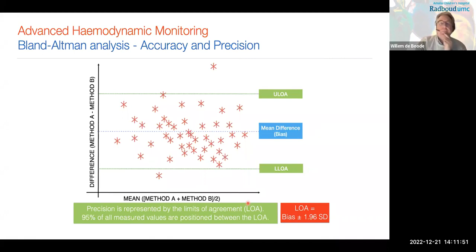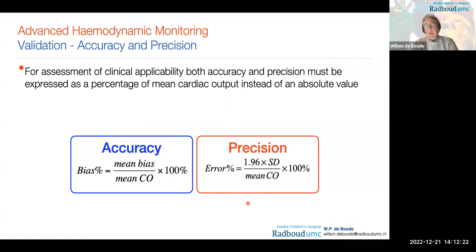So you can have an absolute value, but I think it's very valuable to express it as a percentage of the mean cardiac output instead of only an absolute value. And so you can measure the mean bias. And if you divide that by the mean cardiac output times 100%, that's how you express the accuracy in bias percentage. On the other side, the precision, you can express it as error percentage. That's the limit of agreement divided by the mean cardiac output times 100%. And this is how I would like to explain.